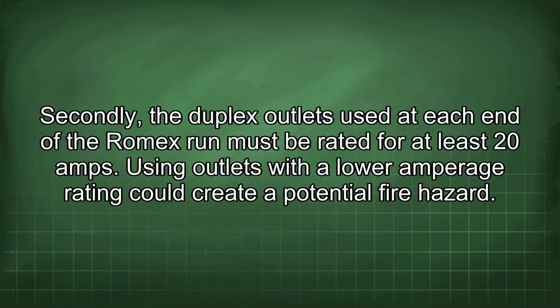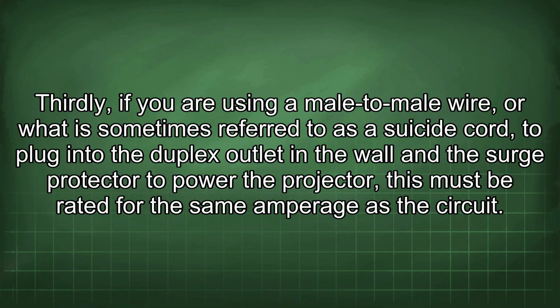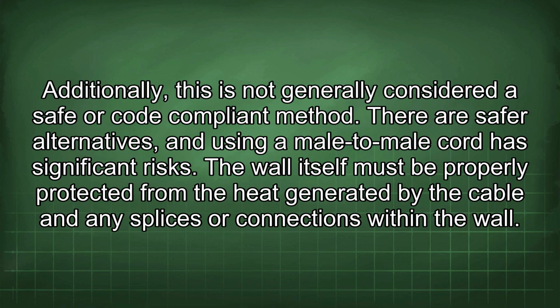Secondly, the duplex outlets used at each end of the Romex run must be rated for at least 20 amps. Using outlets with a lower amperage rating could create a potential fire hazard. Thirdly, if you are using a male-to-male wire, or what is sometimes referred to as a suicide cord, to plug into the duplex outlet in a wall and the surge protector to power the projector, this must be rated for the same amperage as the circuit. Additionally, this is not generally considered a safe or code-compliant method. There are safer alternatives, and using a male-to-male cord has significant risks.